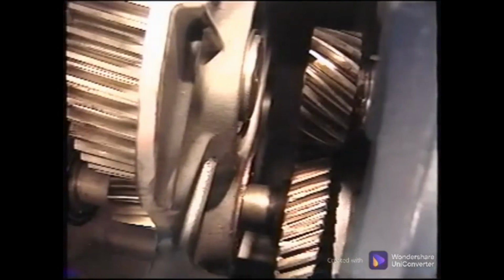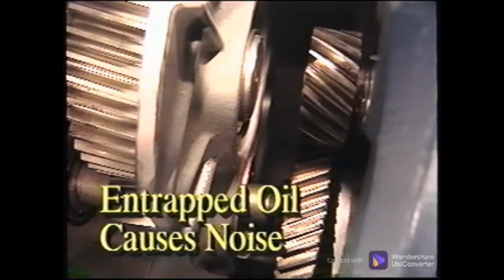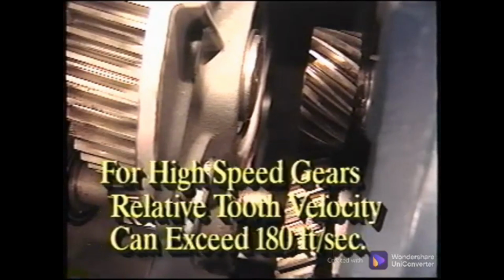When the backlash is too small, oil can become entrapped in the teeth and will be forced out during the meshing action. This oil squirts out with a high velocity, impacting the case and exciting its natural frequencies, causing a loud noise in the gearbox. This is especially true in high-speed gearboxes, where relative tooth velocities can exceed 180 feet per second.